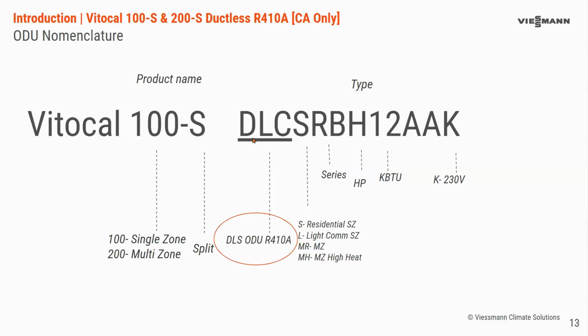The next call out that I like to make is the DLC on the model number. DLC will tell you right there that it's a 410A outdoor unit. Once you see DLC, you already know it's an outdoor unit. The next letter will let you know if it's a single zone or a multi-zone unit. And for those light commercial units, there is an L for light commercial. That also will help you with equipment selection, but it's all laid out in both the price book and the compatibility matrix that we have, so as to make the equipment selection less complicated, if you will.